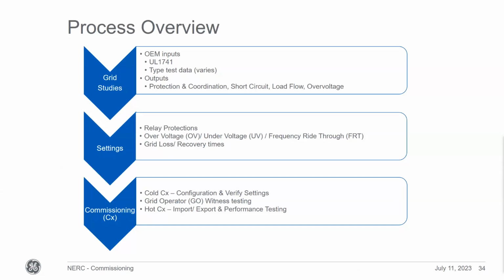What comes out of that on the grid study would be the protection and coordination studies, short circuit studies, the load flow, over voltage type of studies. And as Katie mentioned, the important thing for us as inputs is the settings that come out of that. The settings regarding relay protections, over voltage, under voltage, ride through settings, and then the grid loss, grid recovery time, pretty standard across the nation.